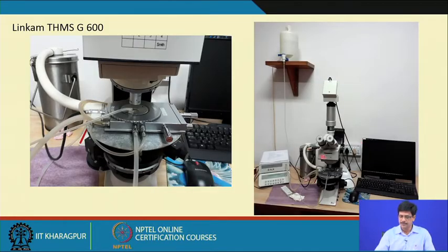This system also needs to be in the configuration in which the model is shown here. It also needs a device for anti-frosting, that means the avoidance of condensation of moisture on the glass windows or on the objective, which will obstruct the optical path, for which nitrogen gas is allowed to flow in the form of a jet, so that it drives off the moisture.